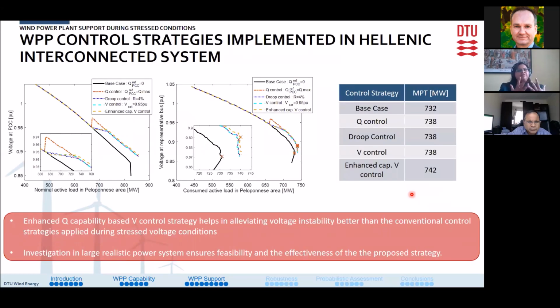To investigate the feasibility and effectiveness of the proposed strategy, as well as the other control strategies, in a large realistic power system, we implemented all the control strategies in the Hellenic interconnected system, and we see from the results here that they are similar to the 3-bus systems. We see an improvement of maximum power transfer when using the conventional control strategies during stressed voltage conditions. However, the enhanced capability-based voltage control performs better and helps in alleviating voltage instability better than the conventional control strategies.